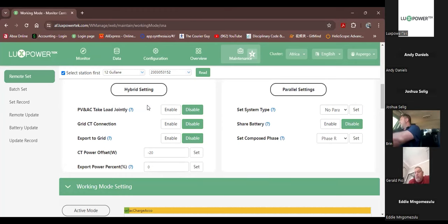It means that the PV and the grid will share the load together during the times that you've enabled it. Essentially, you must remember that this machine is an eco hybrid. The full hybrid can perform multiple functions with PV, battery, and grid at the same time, but the eco hybrid can only either take load from the PV and the battery or from PV and the grid. If you enable this here, it's going to allow you to take PV and grid together.